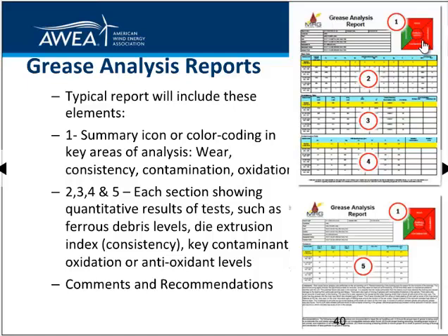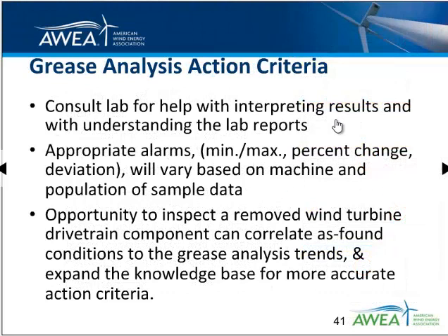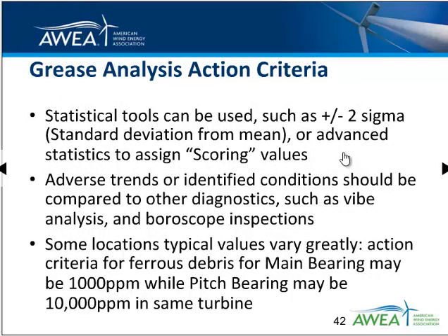Reports can be generated with summary icons giving color coding — red, yellow, green — for wear, consistency, contamination, and oxidation condition, along with monitoring history, trends, comments, and recommendations. When it comes to developing action criteria, consult the lab for help with interpreting results and understanding lab reports. Set appropriate alarms — they might be min or max, or a percent change or deviation, especially in wear trends. If there's ever an opportunity to inspect a removed wind turbine component, correlate that back to the grease analysis trends — that expands our knowledge base for more accurate action criteria going forward.